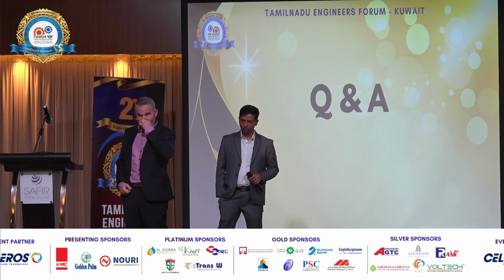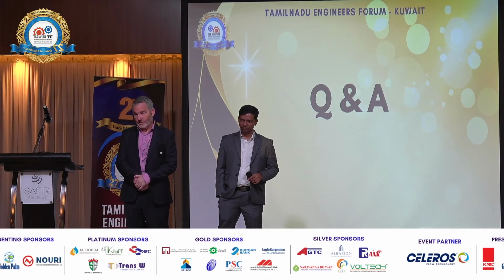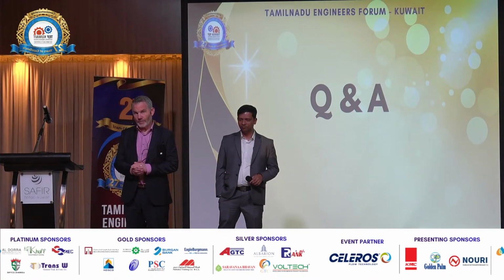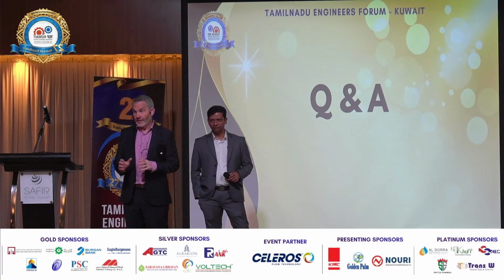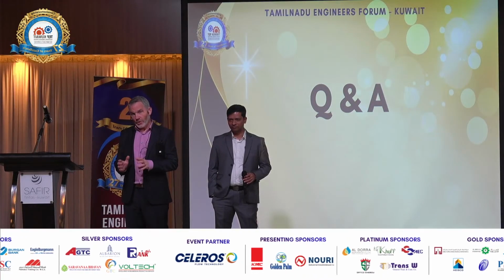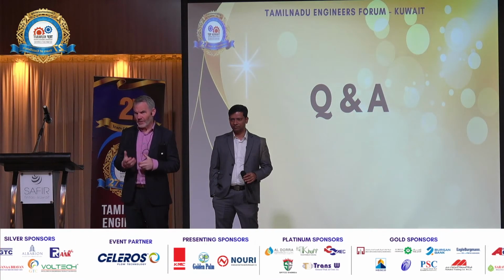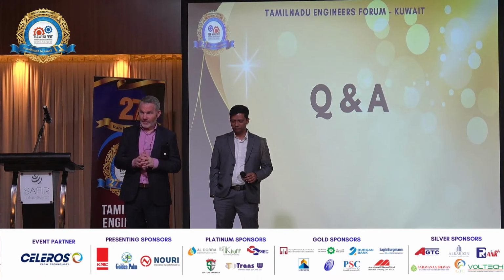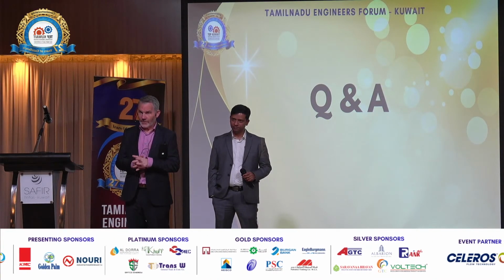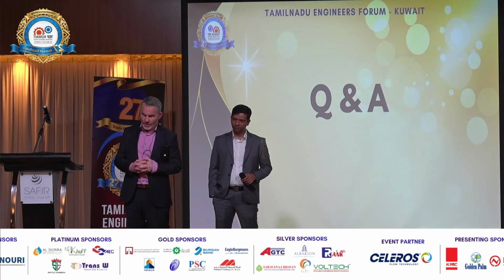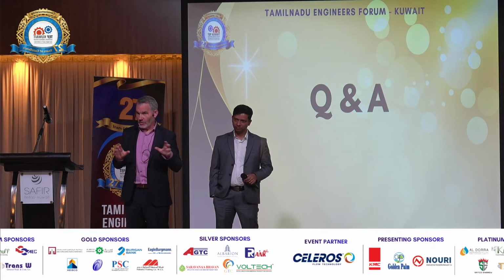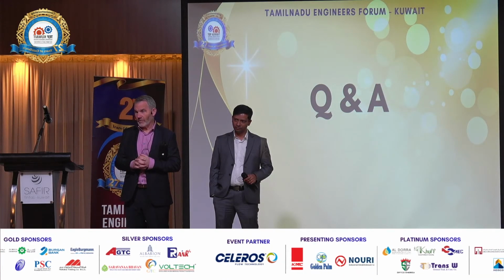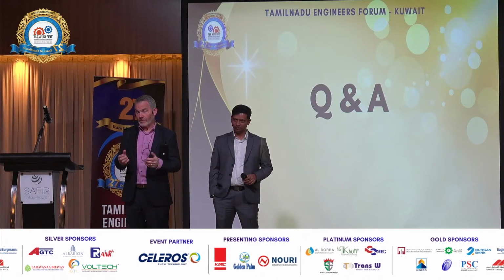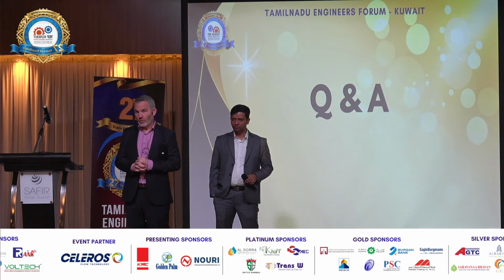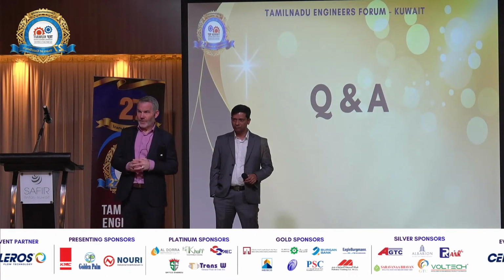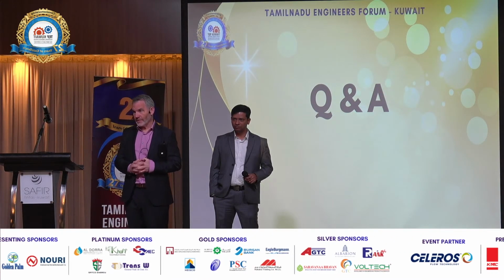I think at 50, 60% you can probably, depending on the specific speed of the pump, if it's a lower flow, higher head, you can get away with that. But on the higher flows, lower heads, higher specific speed pumps, they're more sensitive to running off best efficiency point. So again, it just depends on the actual hydraulic design of the pump. Pumps can run with relatively low vibration at 50, 60%, but they tend to be the lower specific speed pumps.